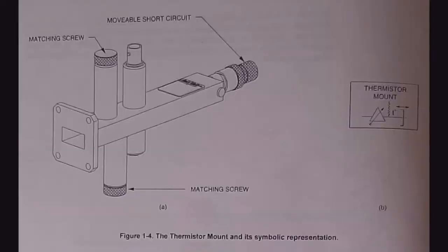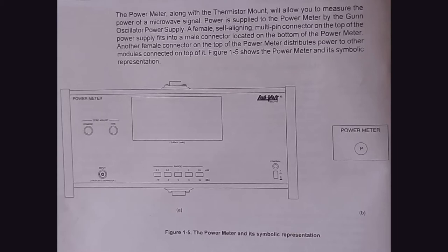A thermistor is a resistive device whose resistance is controlled by microwave energy. When microwave power is absorbed by the thermistor, its resistance changes, which is sensed by the power meter and indicated on the meter's display. Power reception of the thermistor can be controlled by two matching screws; the thermistor mount also has a movable short circuit. The thermistor is an integral part of the power meter — a Wheatstone bridge where three arms are inside the unit and the fourth arm is the thermistor. The meter should always be zeroed using the zero-adjust knob before use.